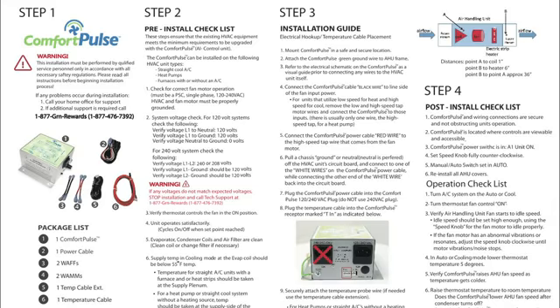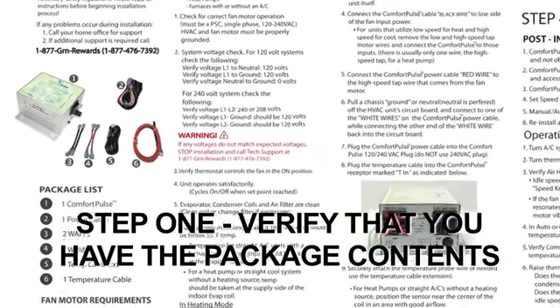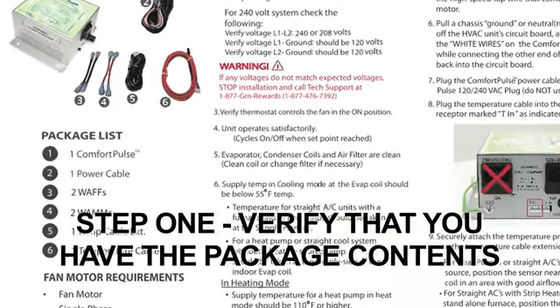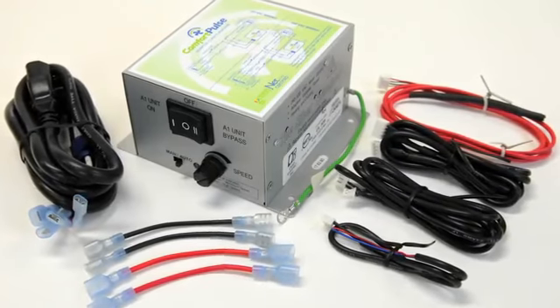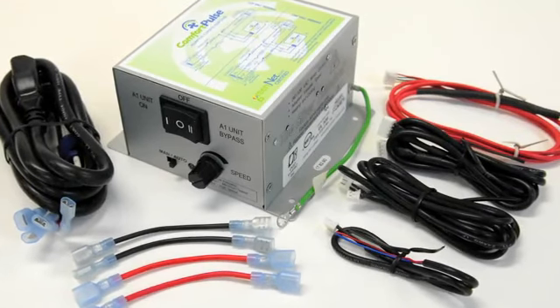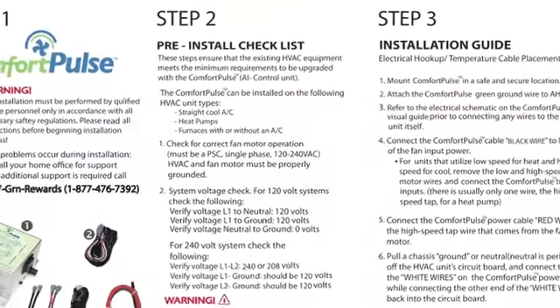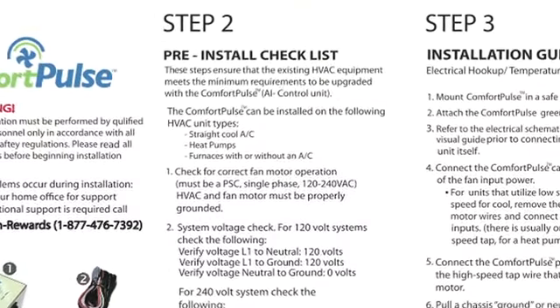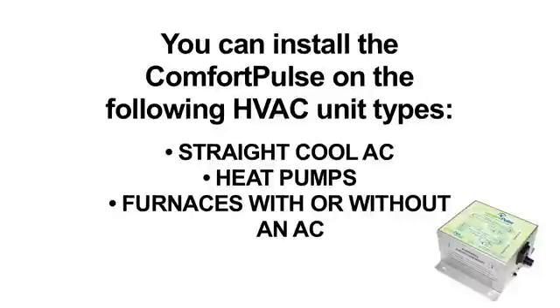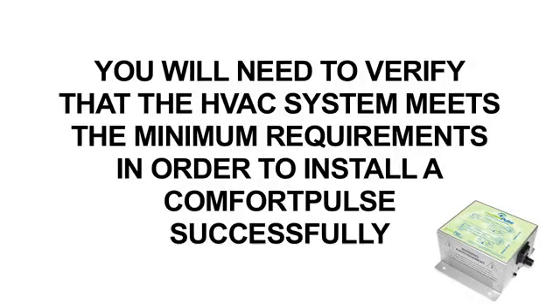Let's get started. First, verify that you have all the proper package contents for your Comfort Pulse. If so, refer to the top of the page on your installation guide marked Step 2. There you will find the pre-install checklist. You can install the Comfort Pulse on the following HVAC unit types: straight cool AC, heat pumps, and furnaces with or without an AC. You will need to verify that the HVAC system meets the minimum requirements in order to install a Comfort Pulse successfully.